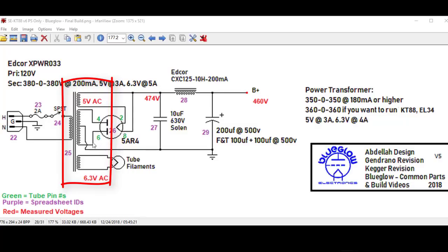Then you have a winding that's your high voltage winding. You can pick a couple different models — I picked one here that's actually 380 volts, then zero, then 380 volts. You might wonder what that means: one side of this transformer, this point right here in the middle, is at zero. In other words, it's a center tap and it's tied to ground right here.